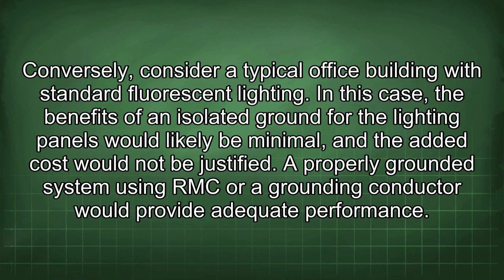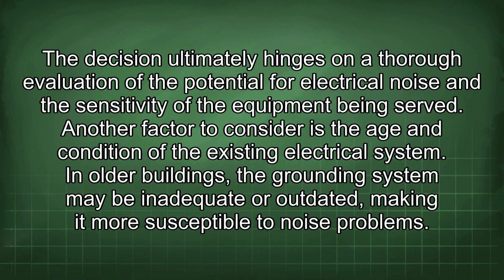Conversely, consider a typical office building with standard fluorescent lighting. In this case, the benefits of an isolated ground for the lighting panels would likely be minimal, and the added cost would not be justified. A properly grounded system using RMC or a grounding conductor would provide adequate performance. The decision ultimately hinges on a thorough evaluation of the potential for electrical noise and the sensitivity of the equipment being served.